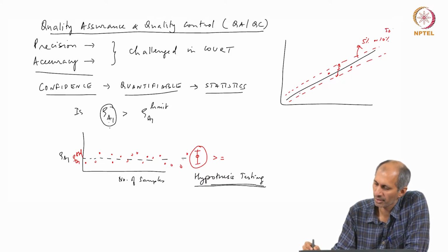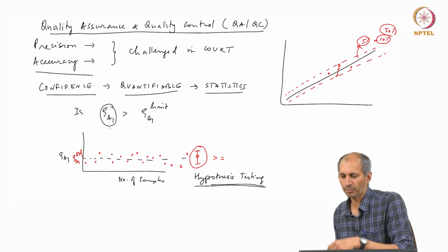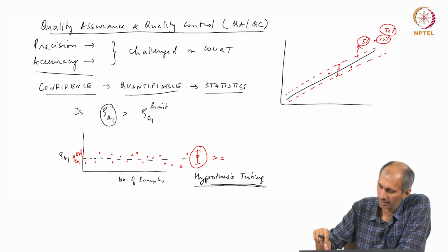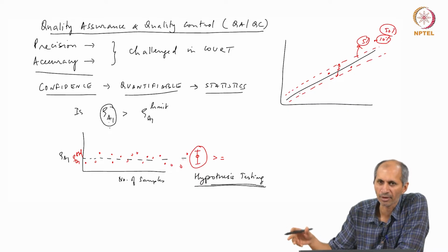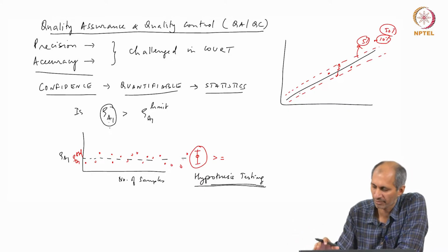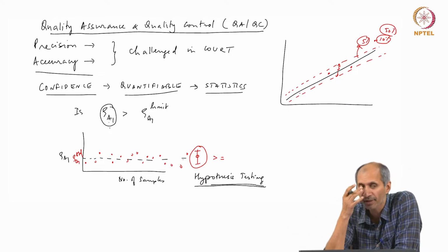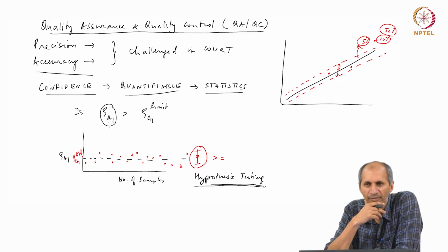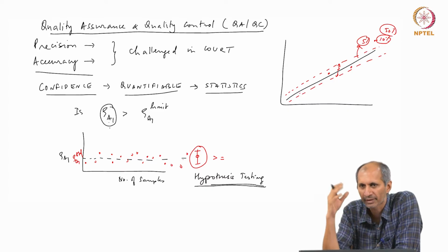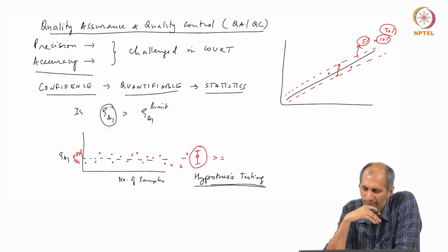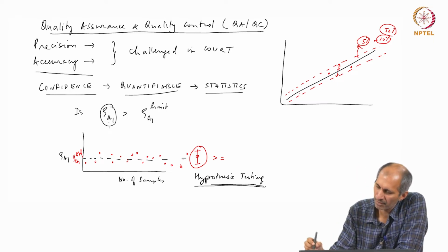Okay. But your choice must be rational. So, how do you choose 5, 10% or 50%? Because if it is possible to get the calibration all the time within 5% of this, you should be able to do it. You should do it. It is going to cost money, it is going to cost effort, but that is fine. But it turns out that in some cases it is not possible to get 5%. You have to expand that. The best you can get is what we use. So, this number is also chosen by you.